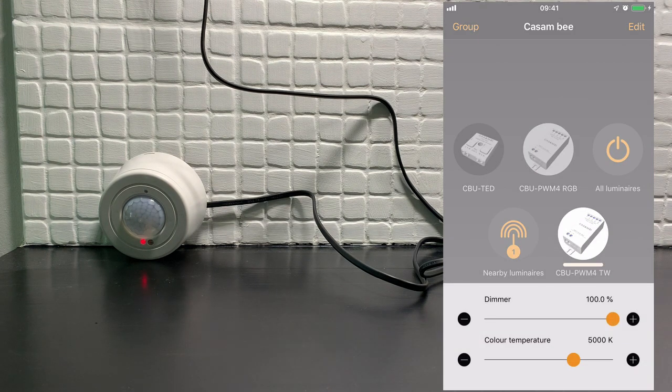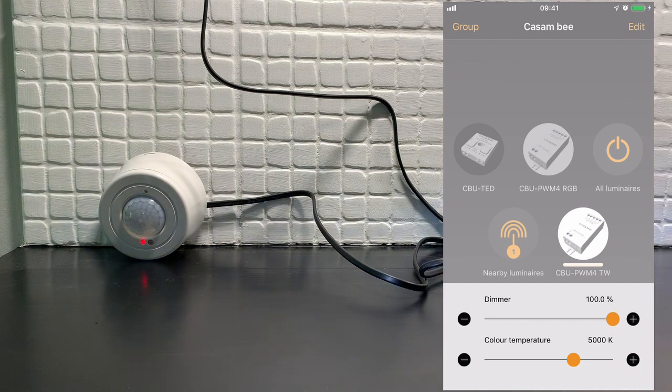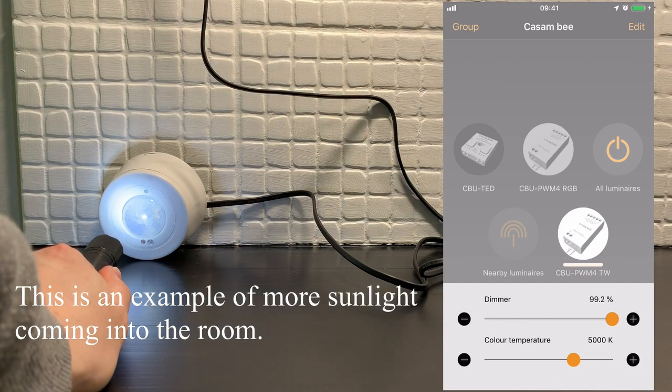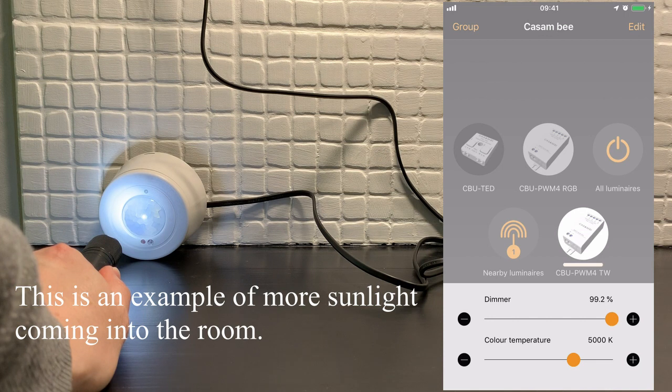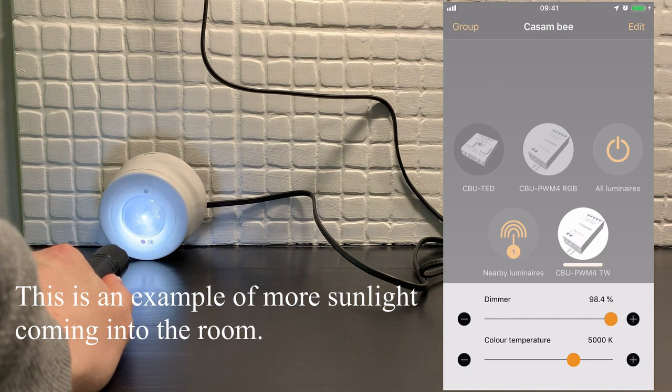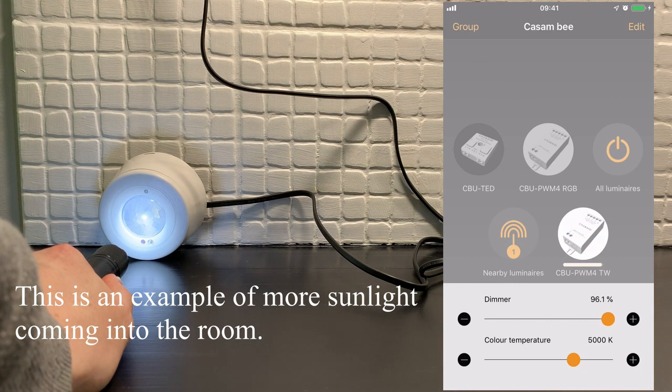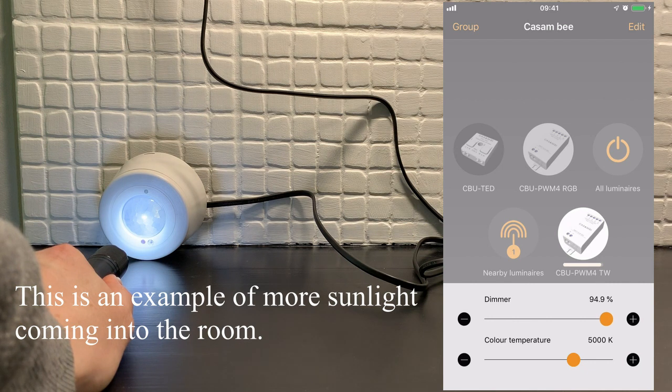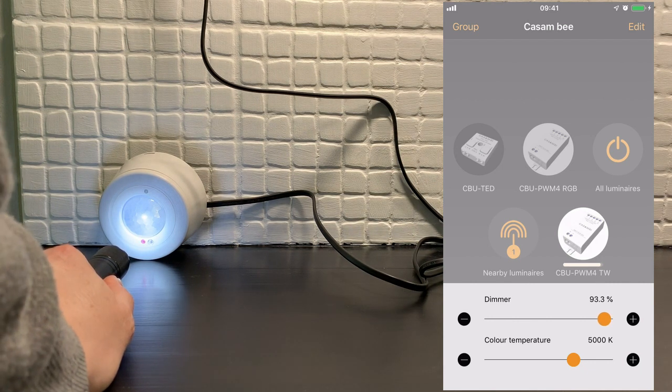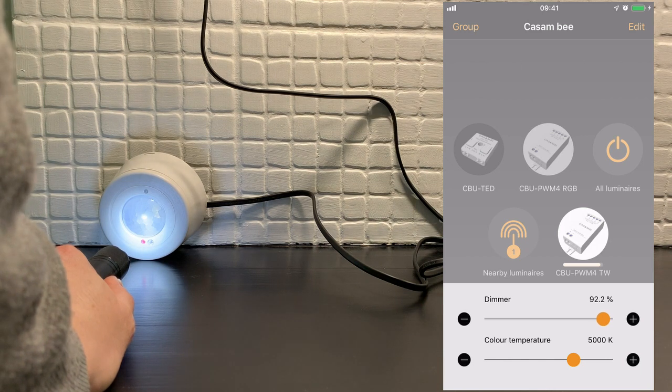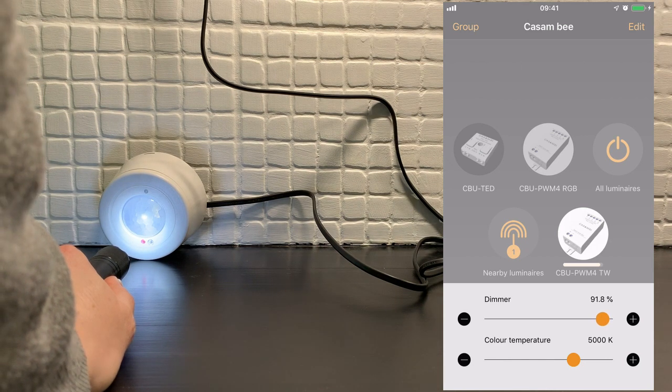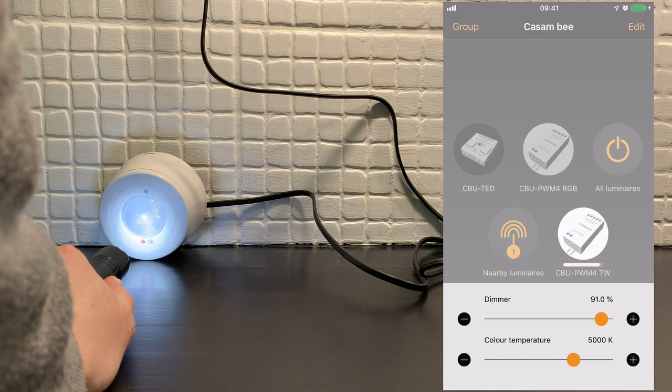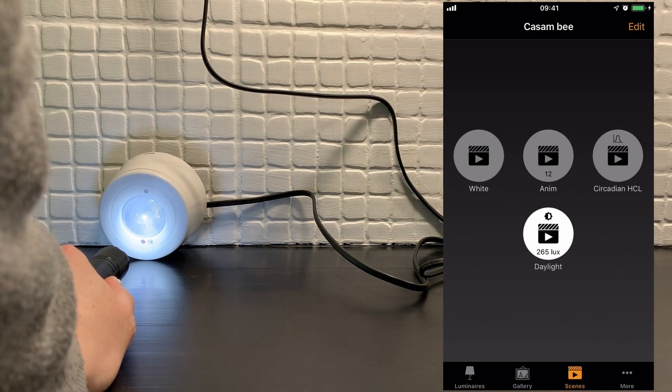As an experiment, I'm going to shine the torch into the daylight sensor. If you now see the dimming level starting to drop. So as the lux value coming into the sensor is now higher, it's naturally dimming the light to try and get the 265 lux value that we set in the scene.